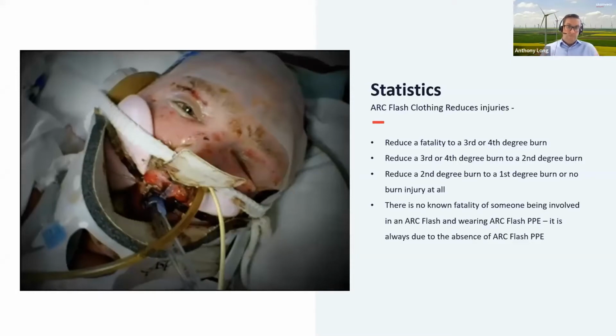So there is no known fatality of someone being involved in an arc flash and wearing arc flash PPE; fatalities are always due to the absence of arc flash PPE. A bit later on, I've got a short video clip to show you what happens when you're not wearing arc flash PPE versus wearing arc flash PPE in an arc flash situation. One of the things to look at here as well is when we do arc flash tests on clothing and fabric, you may be well aware of this already, but the clothing is given an incident energy value, either ATPV, EBT50, or if you're in Europe, to the other side of the Atlantic, you also have now an ELIM value.